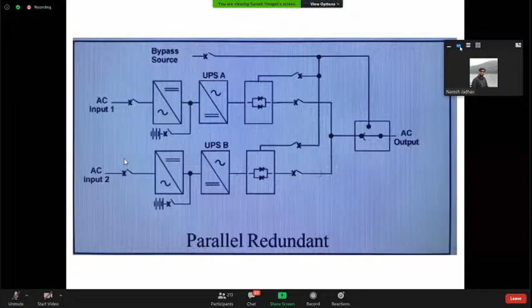If you lose HVAC, what will happen? You don't want to charge the battery. If you don't have this supply, happily you don't face that problem. So when you lose ventilation, in your scheme drawing, it has to trip this breaker. If you trip this breaker, you cannot charge the battery, but you can still feed the load. No problem for feeding the load. Only if you lose ventilation, you will trip the incomer breaker. That is what I have seen.